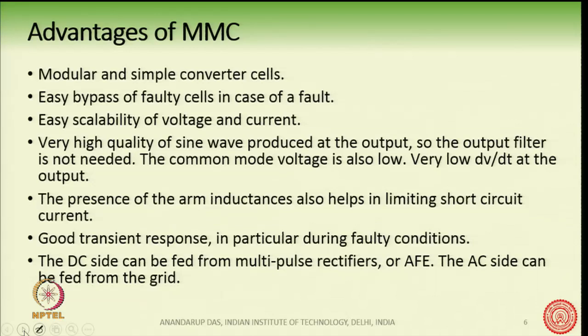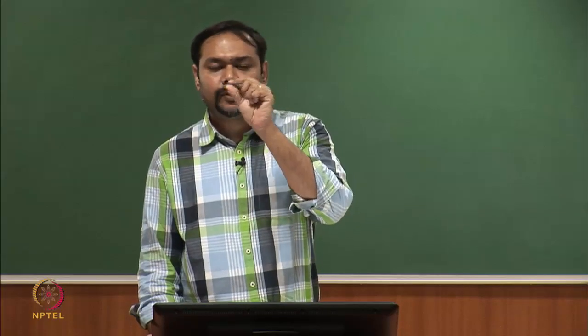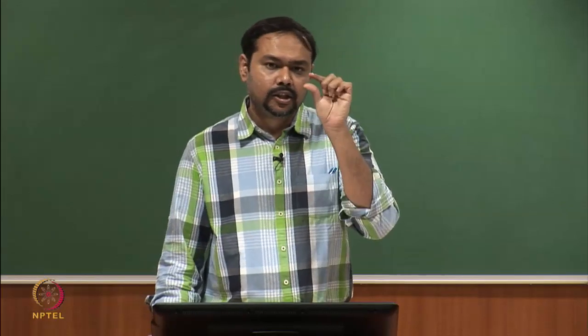Summarizing the advantages: the converter has modular and simple converter cells like a half-bridge; bypass of faulty cells is possible; easy scalability of voltage is possible; and a very high quality sine wave is produced at the output. Using these cells with pulse-width modulation, a very high quality AC waveform can be produced.